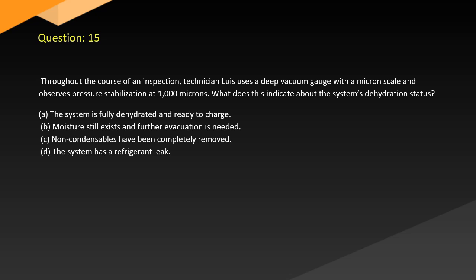Question 15. Throughout the course of an inspection, Technician Lewis uses a deep vacuum gauge with a micron scale and observes pressure stabilization at 1000 microns. What does this indicate about the system's dehydration status? A. The system is fully dehydrated and ready to charge. B. Moisture still exists and further evacuation is needed. C. Non-condensables have been completely removed. D. The system has a refrigerant leak.